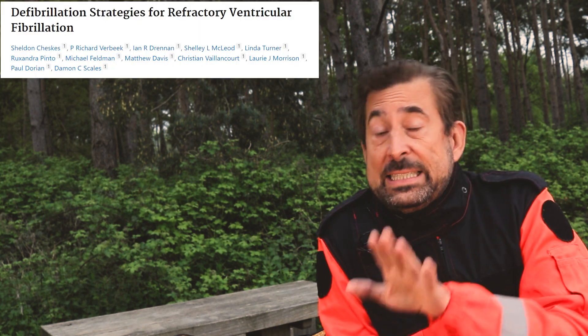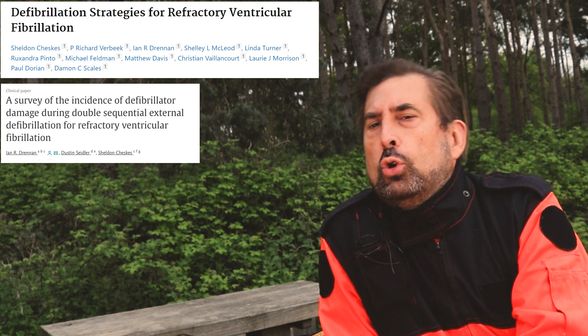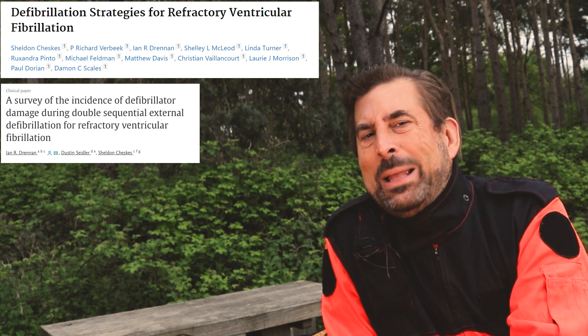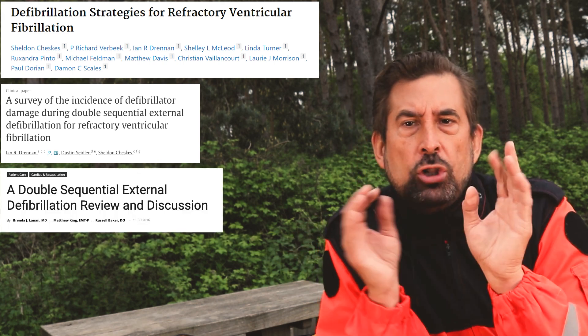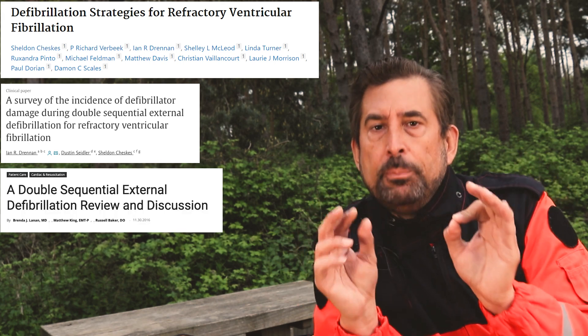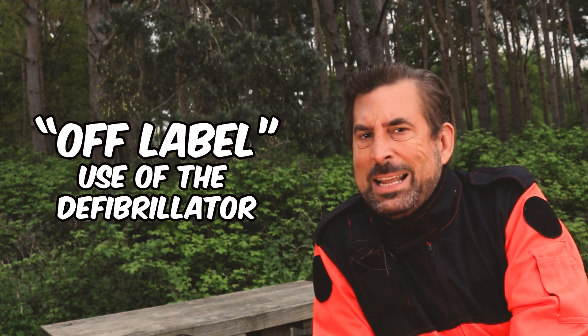Not time to open champagne yet. As of today, the vast majority of defibrillators may not be ready for double shocking. Although Dr. Cheskes states that double defibrillation is equipment-friendly and Dr. Drennan seems to confirm minimal risk to the equipment, a publication by Dr. Lennan points out that small differences in each device's biphasic waveform type may affect the procedure. Furthermore, as dual defibrillation remains off-label use of the defibrillator, it poses challenges not only in terms of warranty but also potential legal liability.